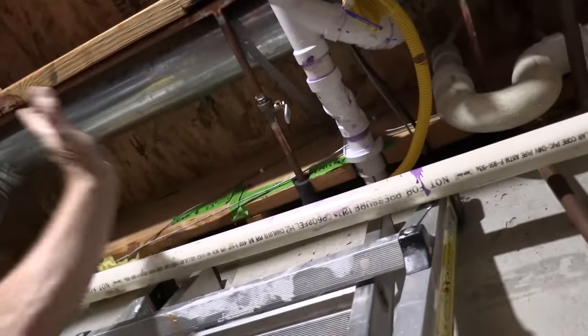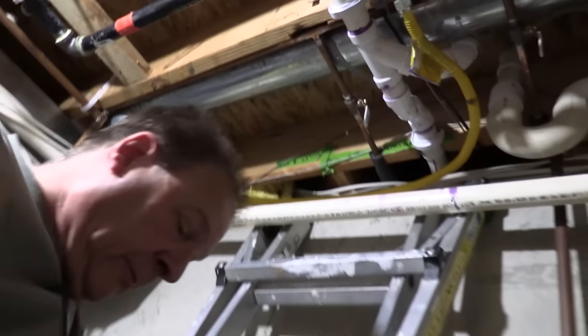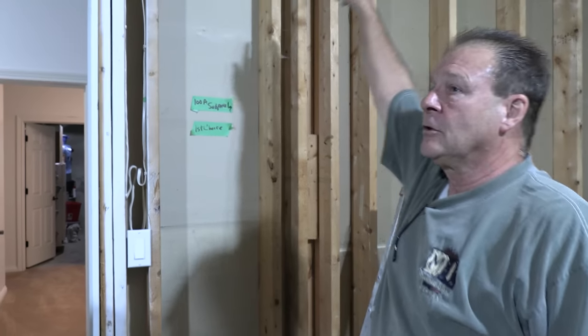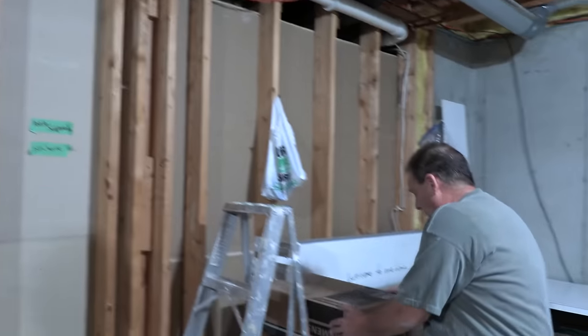If you look here — I tried to pick a spot away from all the rest of it. We're going to come out this way and sweep around, going out around over here. If you go through this channel right here, that channel comes out right here and the planned 100-amp sub panel is right here. You can make a sweeping run come over — I'd suggest this route because then you don't have to go through that blocking over there. We've got a 20-position panel for this — we're only going to install right now a 20-amp 240-volt and one GFI 20-amp, and I'll take it from there.